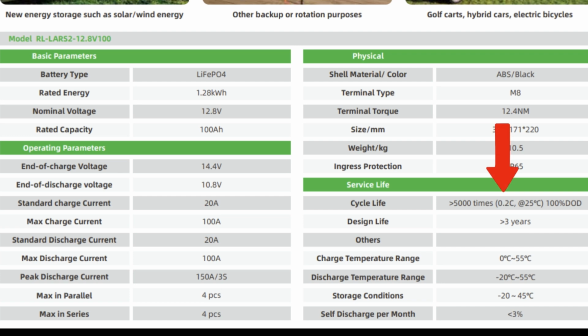This means if you want the battery to last 5,000 cycles, you would need to stay within the recommended charge and discharge rate of 20 amps. It has a max continuous discharge of 100 amps with a 150 amp surge for 3 seconds. You can combine a maximum of 16 batteries in series parallel configuration to create a large battery bank of 20 kilowatt hours.